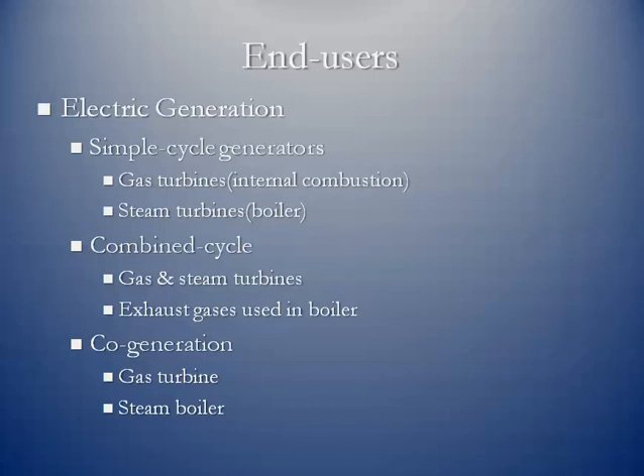Within electric generation, we have different types of generators. A simple cycle generator has gas turbines — these are essentially jet engines, internal combustion, using natural gas as a fuel. Then there are steam turbines, where natural gas goes into a boiler first and creates steam, and the steam is used to push the turbines. You also have combined cycle plants, which use a combination of gas and steam turbines. The gas turbine uses natural gas as fuel, but it has exhaust heat, which is then pumped into a boiler where it creates steam, which drives a steam turbine. Combined cycle natural gas plants are among the most efficient.